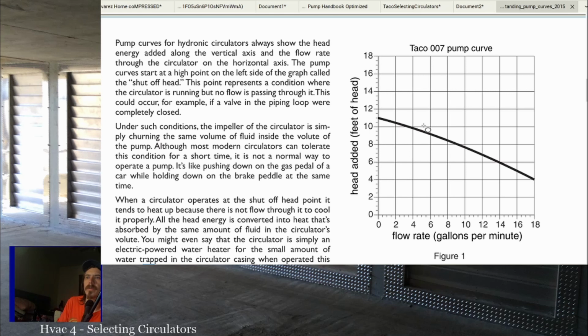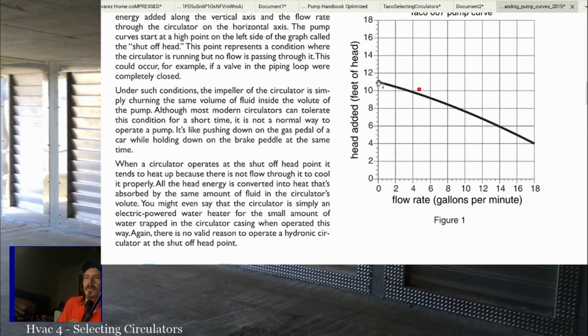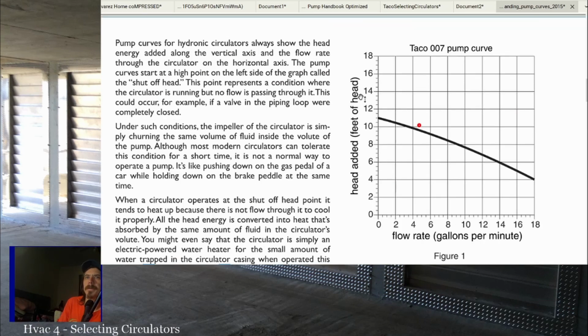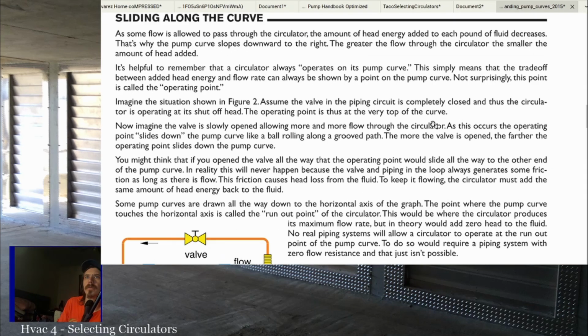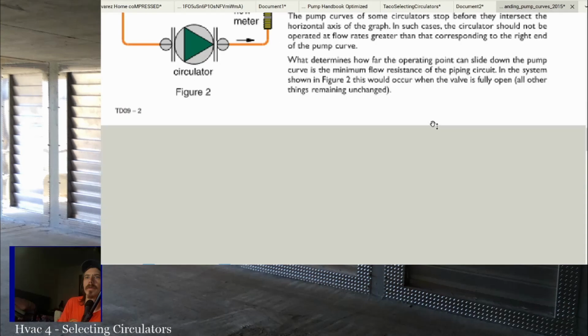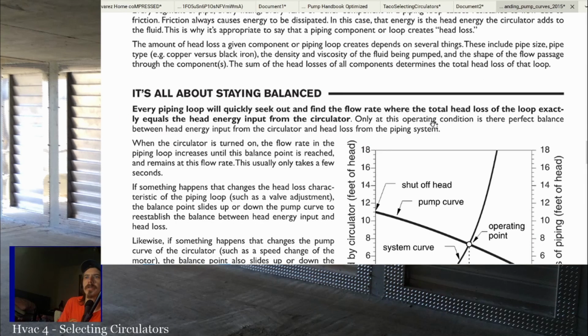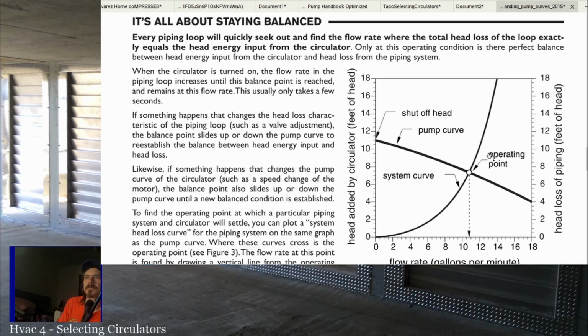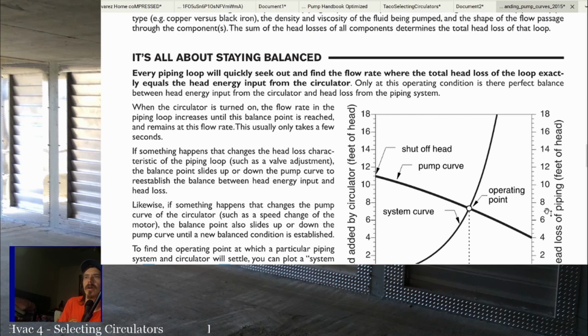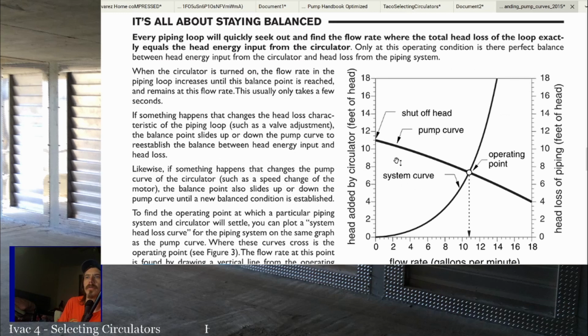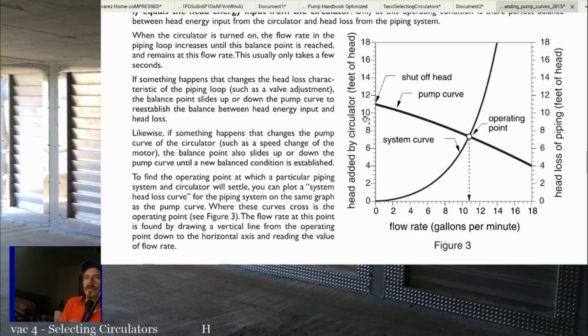And remember that other system where the 007 was close, that system was 4.3 feet of head at 10 GPM. So we were like right here on this 007 pump curve. All right. So you look at that pump curve and you'll move along the curve. We got another picture here to go by. All right. So you'll have the shutoff head, right? This is the pump curve. Shutoff head is the end of the curve over here, right?